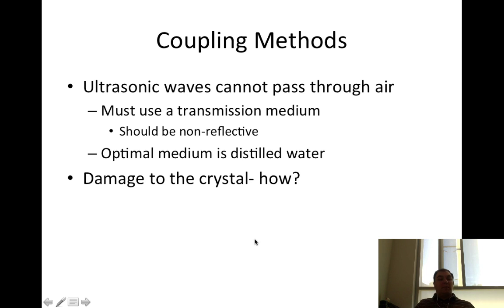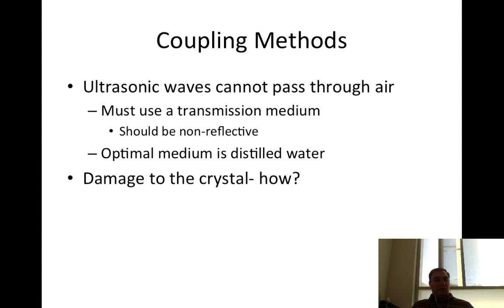Ultrasonic waves cannot pass through air, so you must use a transmission medium. It should be non-reflective. The optimal medium is distilled water, though nobody uses that — everyone uses ultrasound gel, which you buy from a medical equipment catalog.